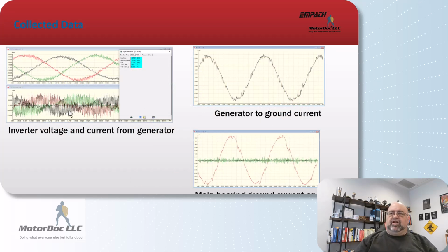This is the voltage and current from this type of generator. It was an induction generator. So it puts out the data at whatever frequency, then it goes down tower, and this is the type that has the inverter between the generator and the grid. They make up less than 6% of all the turbines. This is the generator where I showed the current clamp on the generator. That is about peaking at about 30 amps. Now, when I do these studies, we go off the peak current. And this is at the ground for the main bearing, and that's at 148 amps.